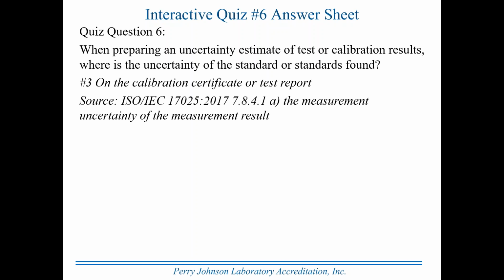The source, and again, this is right out of the standard, the measurement uncertainty of the measurement result. This is in the section of the standard talking about reporting results. What has to be on a calibration result? The measurement uncertainty of the measurement result. Now, I told you that in the 2005 version, it had to be on the report unless a statement of compliance was made. And if a statement of compliance was made in the 2005 version of the standard, then whether you put the uncertainty on the certificate or not was optional, because it had already been determined and already been used by the laboratory, applying it to the result to evaluate compliance with specification.